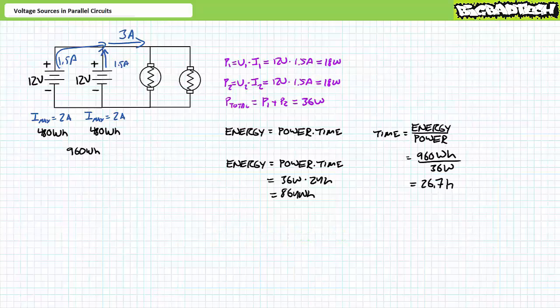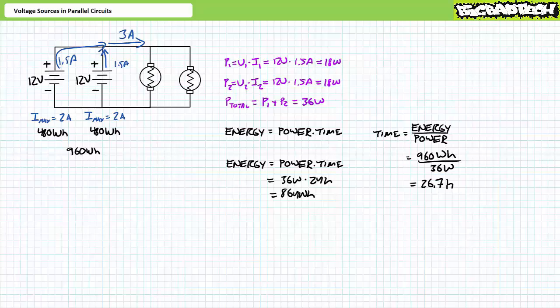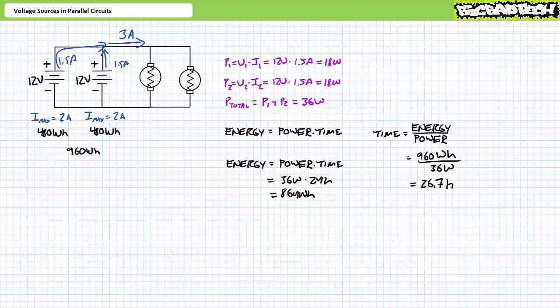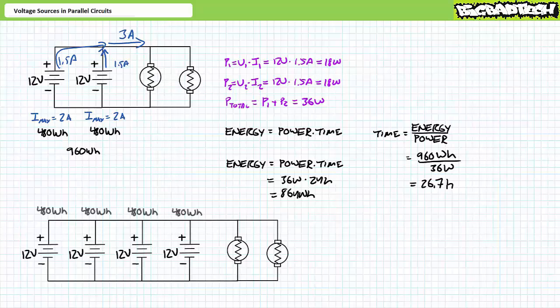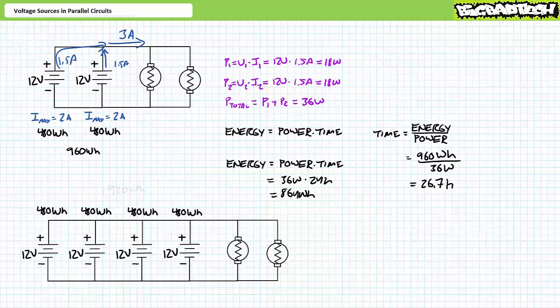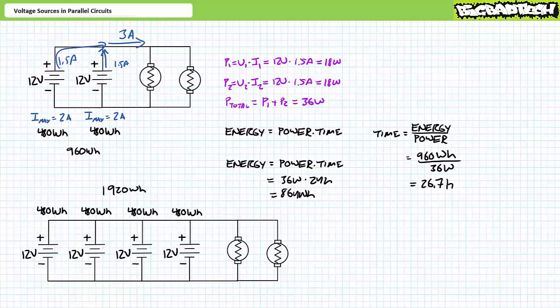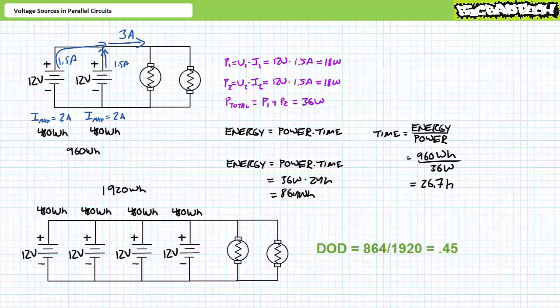Let's say we wanted to provide a more reasonable depth of discharge to ensure battery longevity and, in an emergency, provide at least two full days of autonomy for the system. Autonomy, by the way, is a measure of how long a battery bank can supply power without a charge. If two batteries in parallel provide slightly more than one full day of autonomy, it stands to conjecture that four batteries in parallel can provide slightly more than two full days of autonomy. This larger battery bank now contains 1920 watt hours, or roughly 1.9 kilowatt hours. As previously, a full day of use results in the expenditure of 864 watt hours of the available 1920 watt hours, bringing these batteries to a more reasonable 45% depth of discharge, considerably lengthening their lifespan.